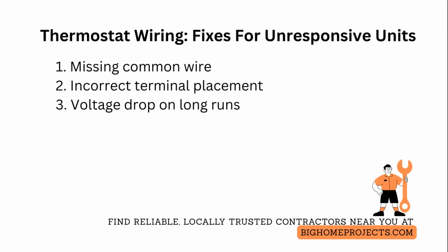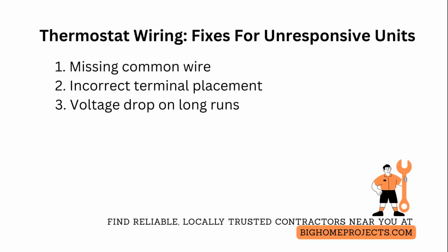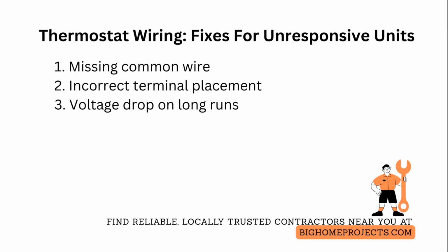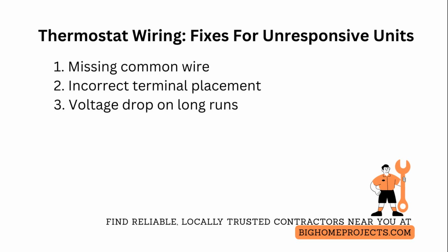One of the most common thermostat wiring mistakes is a missing common wire causing no power for smart thermostats. Fix this by running a new conductor from the furnace control board common terminal to the thermostat location or install a power adapter kit that provides a stable common.